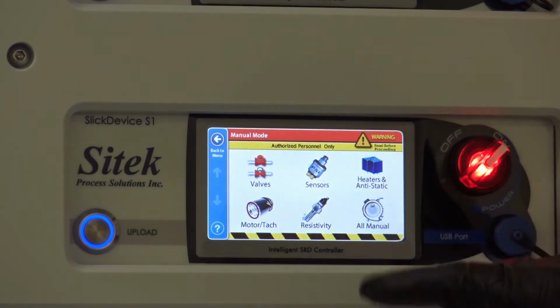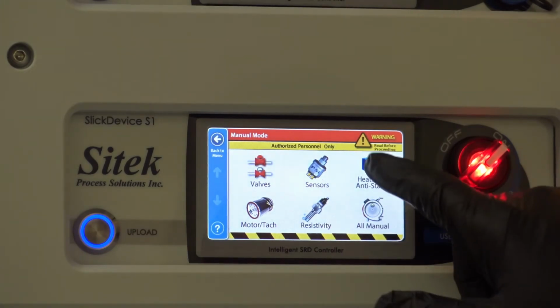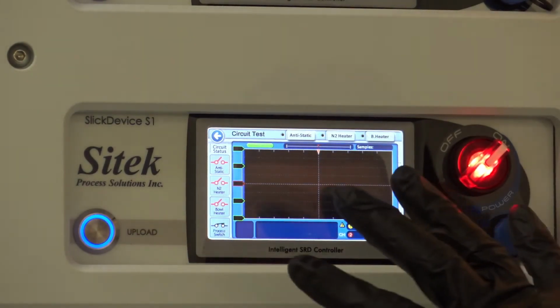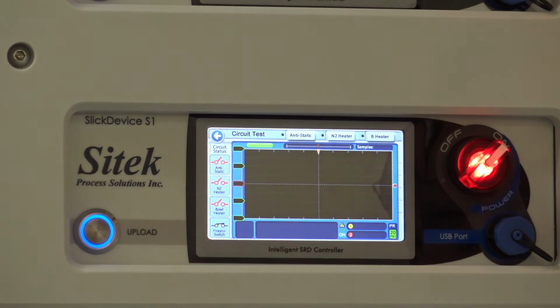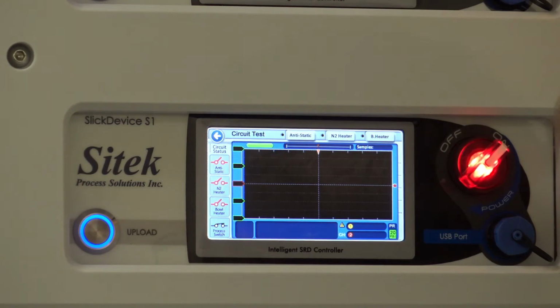What we can do here is one of the huge features of our system, our circuit test. We monitor the antistatic module, the N2 heater, and the blanket heater. One of the main enhancements of our controller is that we have a special DDL algorithm generated by Sitek that has a way of letting you know if your antistatic module is working. It's proprietary, so we can't go into how we've done it, but it monitors it, and you'll see in a second.